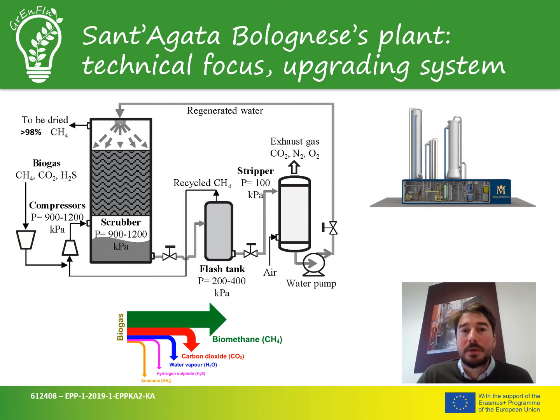There are three columns: the absorption column, the flash tank, and the desorption column. In the first column, the absorption column, also called scrubber, the biogas is showered with water that dissolves the CO2, which has a higher solubility in water than CH4 at that pressure. It's a pressure between 9 bar and 12 bar.